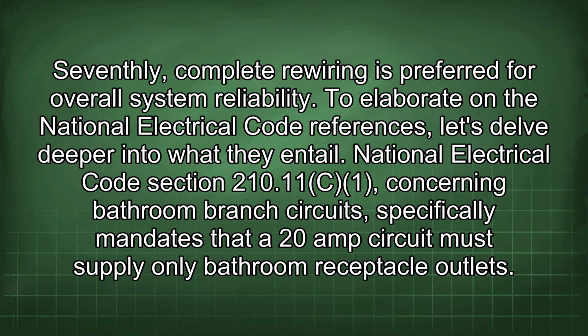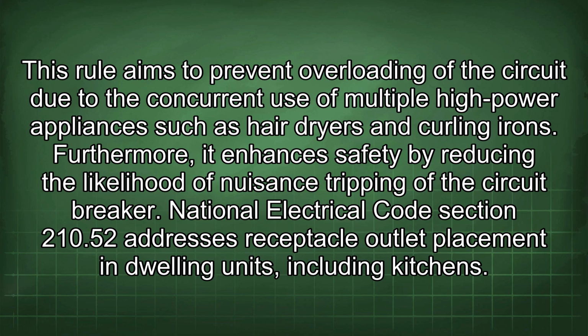National Electrical Code Section 210.11(C)(1), concerning bathroom branch circuits, specifically mandates that a 20-amp circuit must supply only bathroom receptacle outlets. This rule aims to prevent overloading of the circuit due to the concurrent use of multiple high-power appliances such as hairdryers and curling irons. Furthermore, it enhances safety by reducing the likelihood of nuisance tripping of the circuit breaker.